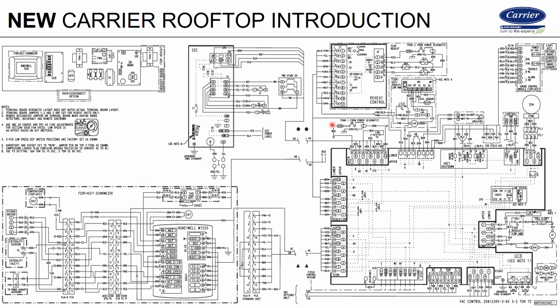Okay. So what happens is if that opens at 160 degrees, it basically resets the IGC board. The IGC board is capable of storing fault codes. It will store limit faults, and I'll go through all those, rollouts, all kinds of different fault codes. But as soon as you cycle power to it, you clear them all.